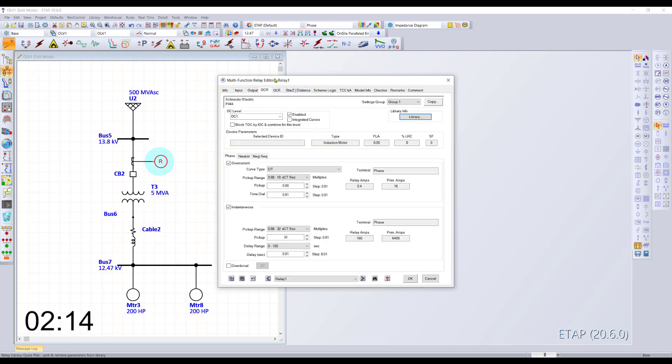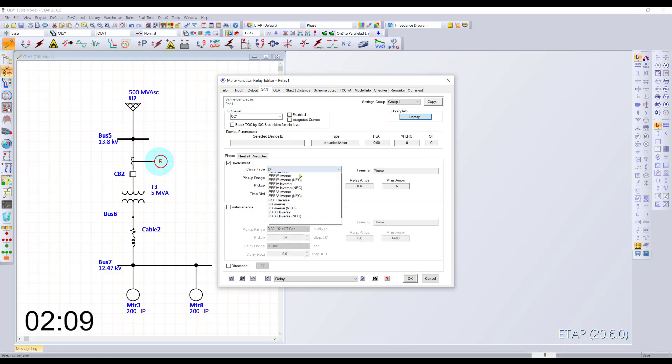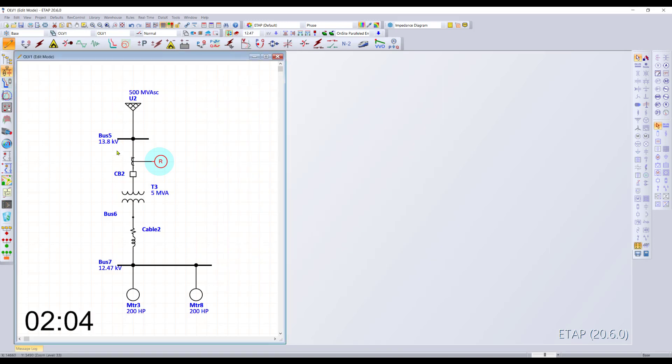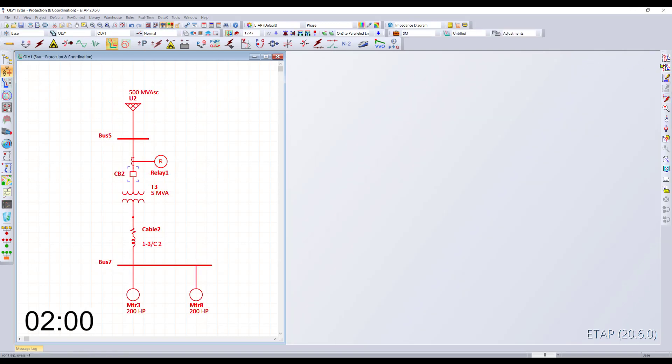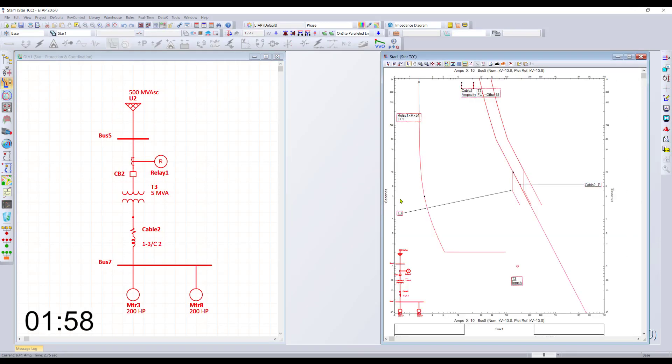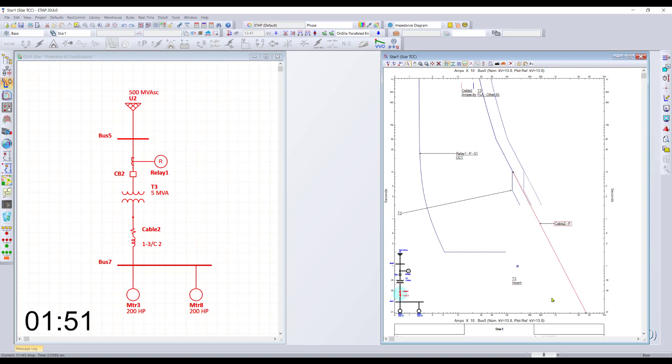You can specify all those details. We'll turn off the instantaneous for the time being and set our curve to an IEC curve. We can now select this entire diagram and plot it into our TCC. We can see the relay curve, the cable damage curve, the transformer damage curve, and the motor curve.